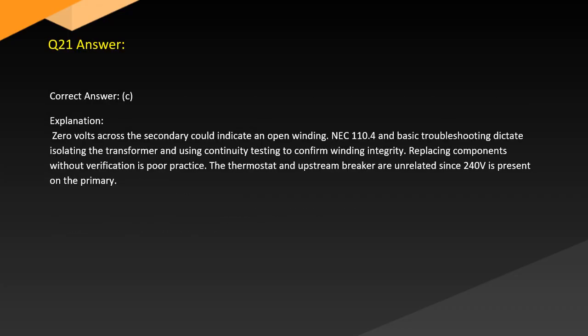Answer. Correct answer: C. Explanation. 0 volts across the secondary could indicate an open winding. NEC 110.4 and basic troubleshooting dictate isolating the transformer and using continuity testing to confirm winding integrity. Replacing components without verification is poor practice. The thermostat and upstream breaker are unrelated since 240 V is present on the primary.